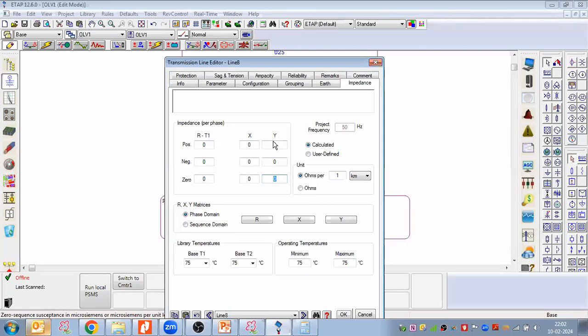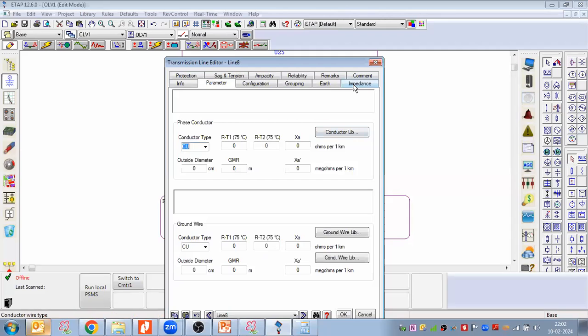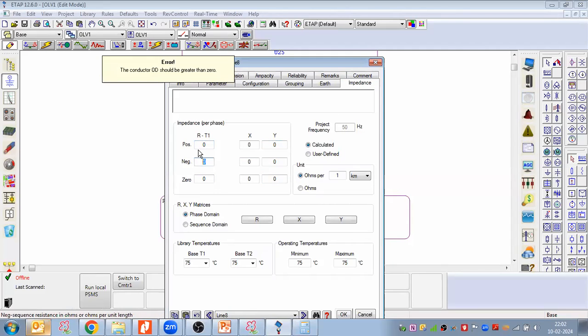In a real-time project, we don't go with these manual parameters. Instead we use the transmission line parameters like positive sequence, negative sequence, and zero sequence. Since a line is static equipment (unlike a motor, which is dynamic), the positive and negative sequence components are identical, so whatever value I put for positive, I copy to negative. The zero sequence component is approximately three times higher than the positive component.